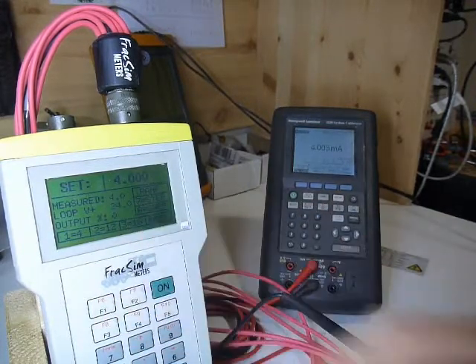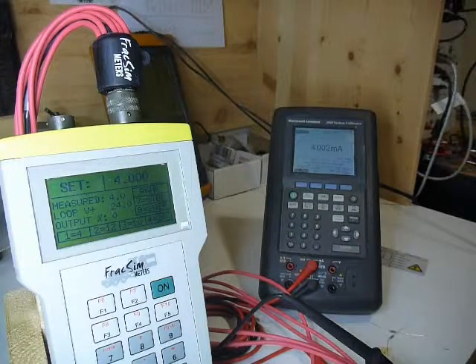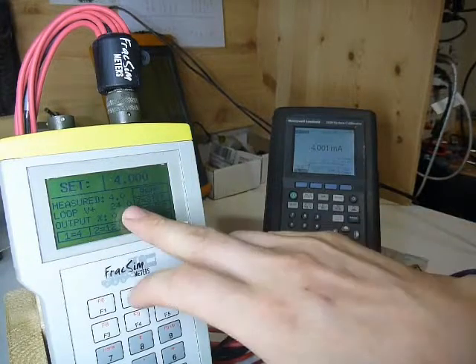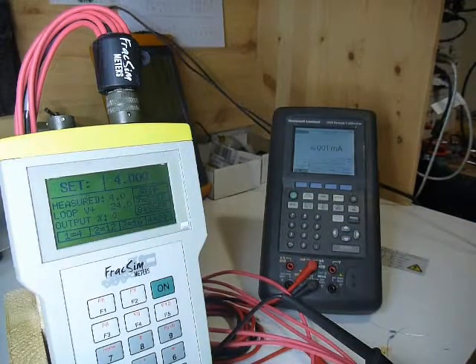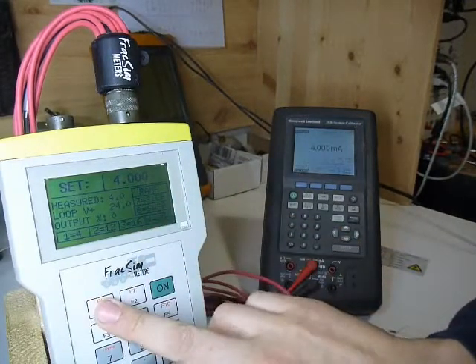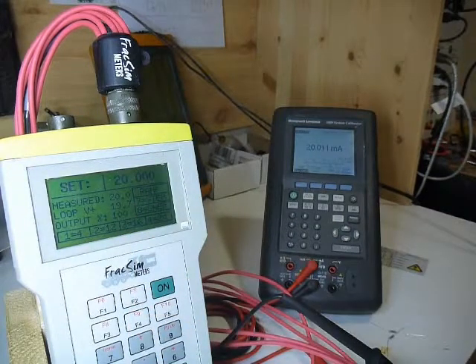But again, it's just an indication to show you more troubleshooting indicators that you could use to properly judge whether your loop is working correctly. For example, if you knew the resistive load of what your PLC was, or whatever pressure recording device or analog readout you're using, if you knew the resistance of that, you can see the voltage drop when you go from the different values and get another assessment of whether everything's working correctly.